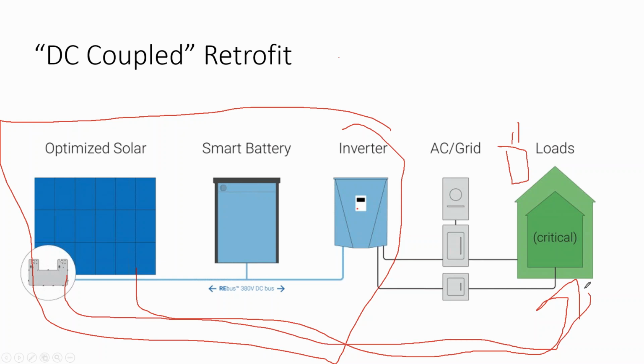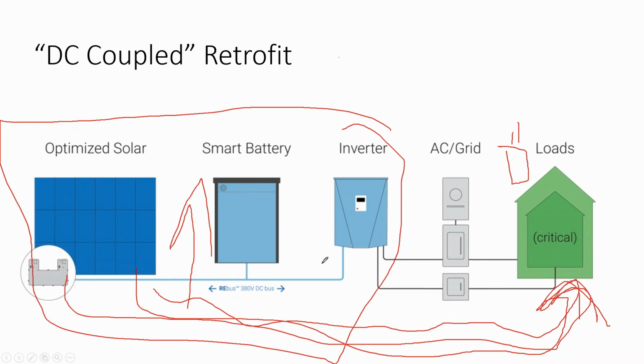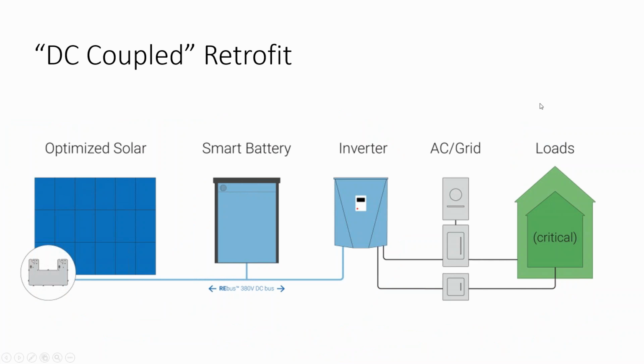On very far away ground mounts, I really like the SolarEdge solution because it steps up the voltage to 600 volts-just like high voltage power lines, you want high voltage for transmitting electricity over long distances. So I might do an AC coupled SolarEdge system to push that and get stepped-up voltage at the distant ground mount array. The takeaway is there's no hard and fast rule of thumb on which is better, DC coupling or AC coupling.